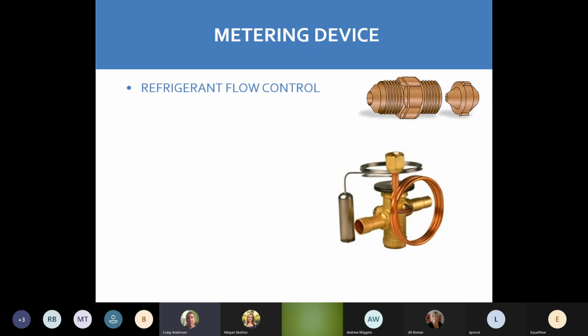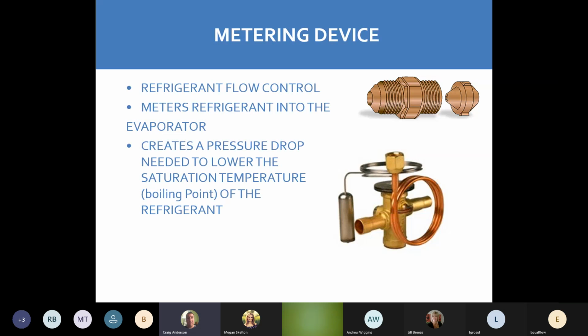So metering device, refrigerant flow control. It's bringing our Freon to our coil and monitoring it going through the coil. It meters refrigerant into the evaporator coil. It creates the pressure drop needed to lower the saturation temperature, the boiling point of the refrigerant. That's what our metering device is doing in our coil. 2 basic types: fixed, which is our piston, and adjustable, which is our TX valve.